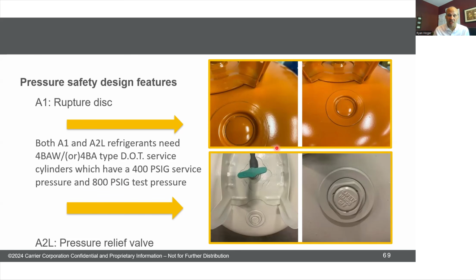So because of those things, the left-hand thread, this relief valve, that does drive up the price of the refrigerant. The other thing, and I'm sure you guys are all painfully aware, is that it's been difficult to get 454B, or at least it was this spring and early summer. Now it seems to be okay-ish. But it was difficult to get R-454B, and it wasn't because there wasn't enough actual refrigerant. It's because they couldn't get enough tanks that had this relief valve on it. Whoever did the estimate on that didn't predict how many tanks they needed, or couldn't get the valve, or whatever their reason was, and hence no one could get tanks.